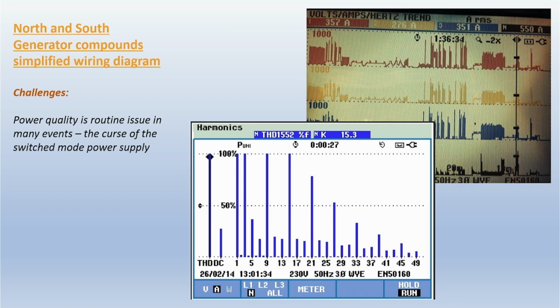When you add all of this together, the demands on the temporary system can be quite challenging. So although we're using less energy, the way we draw that energy from the supply is much more of an issue. Some of the odd order harmonics can cause overheating in alternators.